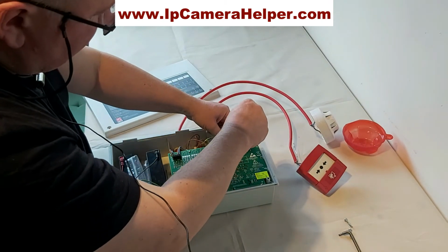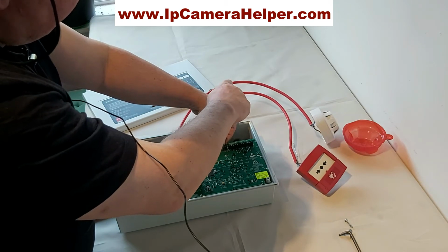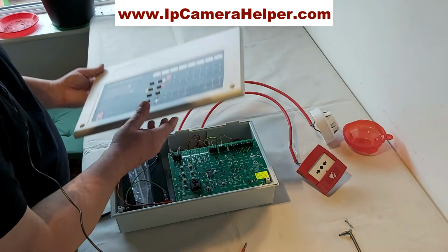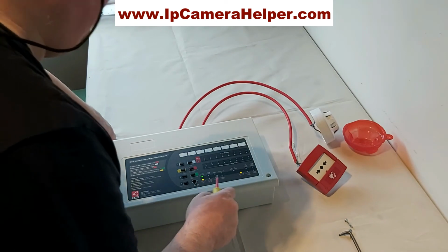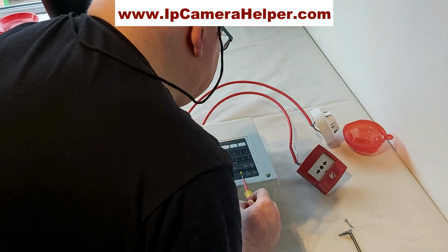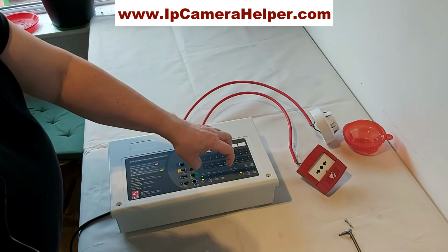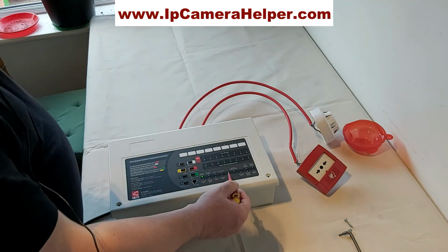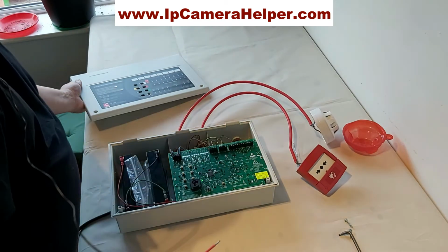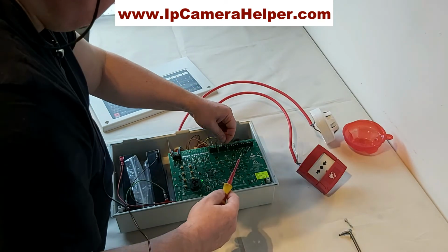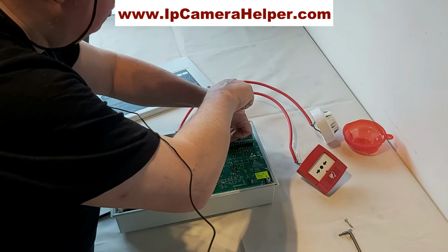So if I disconnect one leg of this resistor on the fourth sounder line, it will start complaining. And here we have, again, general fault, and it says sounder status. So there's a problem. Anytime there's any orange or yellow light, there's a problem with something. So again, we now have a sounder fault. To fix it, there's no point in resetting the panel. We have to first connect it properly. In short, we have to fix the problem.